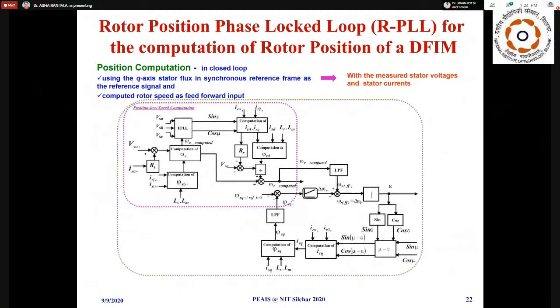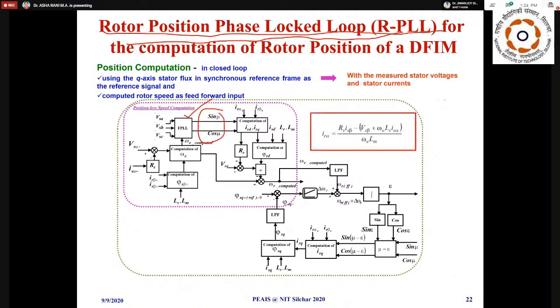Easily we can find out using only the stator voltages and currents. This method is generally called rotor position phase lock loop, RPLL, similar to the grid side PLL. Using the normal grid side PLL, we can find sin mu and cos mu. Also, there's no need to actually use rotor sensors — instead of measuring, we can compute the rotor currents.